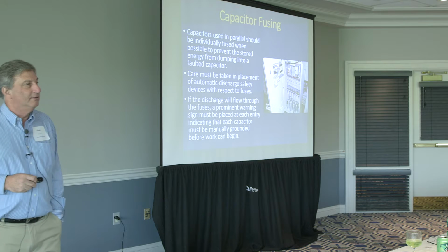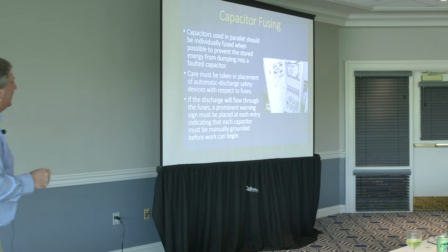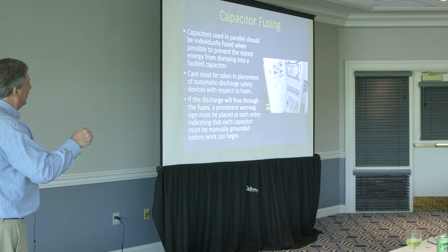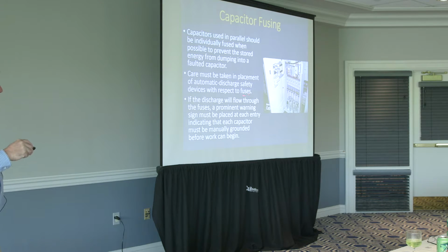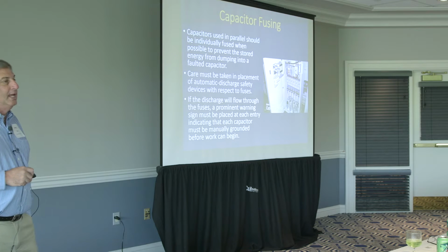Capacitor fusing. Okay, that becomes important. How you fuse those capacitors. Because if they're in parallel, okay, individually fused to prevent the stored energy from dumping into a faulted capacitor. So there are things like that you take into account when you install them. Care must be taken in placement of automatic discharge safety devices with respect to fuses. If the discharge will flow through the fuses, a prominent warning sign has to be placed at each entry indicating each capacitor must be manually grounded before work can begin.